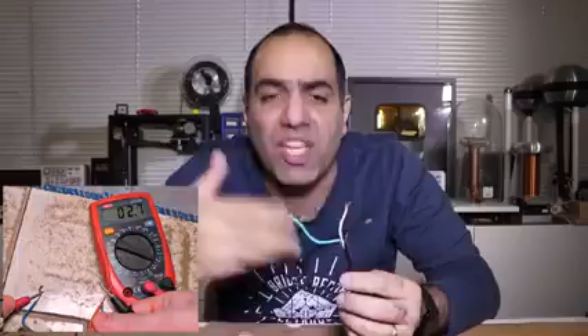Right now I'm reading around 240 millivolt AC between neutral and earth, which translates to around 4.5 volts at the output of the transformer. Now if I turn on my soldering iron and blowtorch to draw much more current from the power lines, the voltage difference changes to around 700 millivolt AC, which is like 10 volts at the output of the transformer.